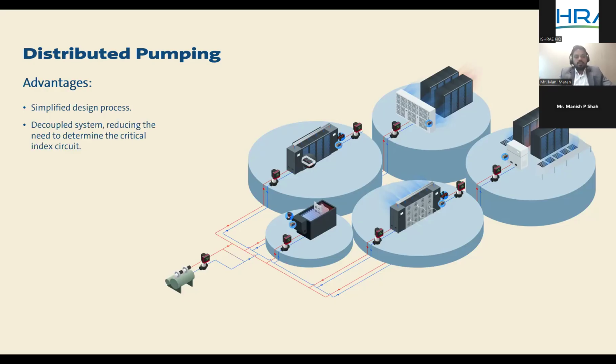And a decoupled system reduces the need to determine the critical index circuit. When we decouple the primary and secondary and have two different sources or drivers, it is very easy to determine where we have the critical load and to address that critical load. So these are some of the advantages that we can see in distributed pumping. And modular design. As I said, a data center needs a modular approach. The data center progresses as more load is added to the server. So even our design is modular. When the load gets added, we can add our source and driver, which makes the system more efficient and more flexible to operate.